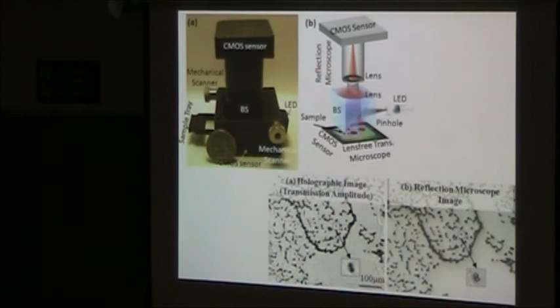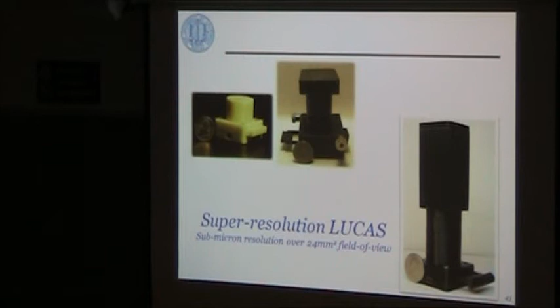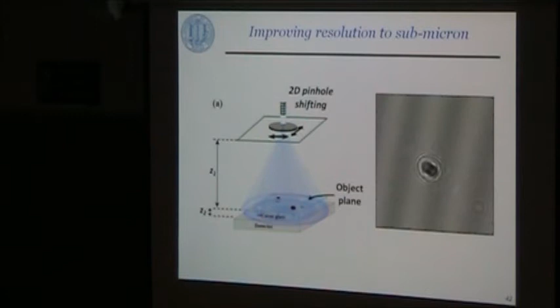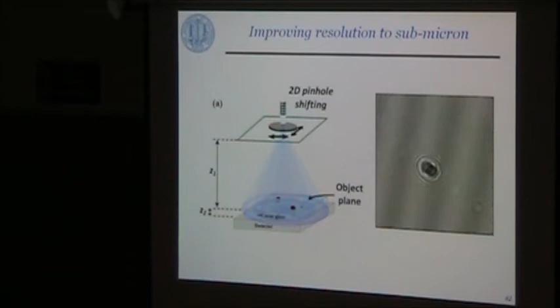So rather than using a single light emitting diode as shown here, I'll switch to another design here, which has the same CMOS imager, the same field of view, the same pixel size, but has a modified architecture here to really go to sub-micrometer resolution, close to a numerical aperture of 0.5. The key for this is actually to shift the source. So if you shift the source, and if your sample inserted from the side, let's say, is stationary, like in a blood smear or some water sample, then as I shift this by small amounts, like 100 micrometers or so, my hologram, which is static, will be shifting by a couple of microns. And each time I'll be undersampling this same hologram, lens-free hologram, by the same pixel size.